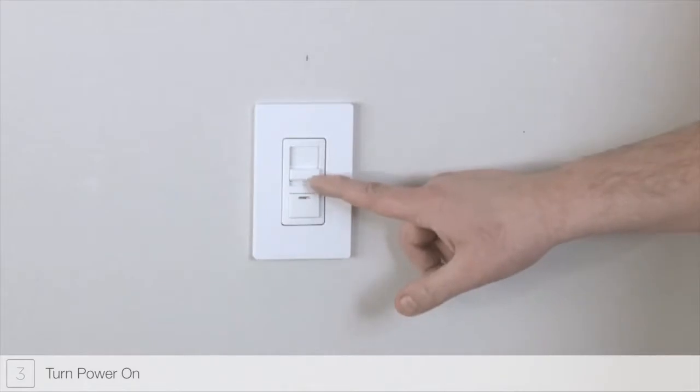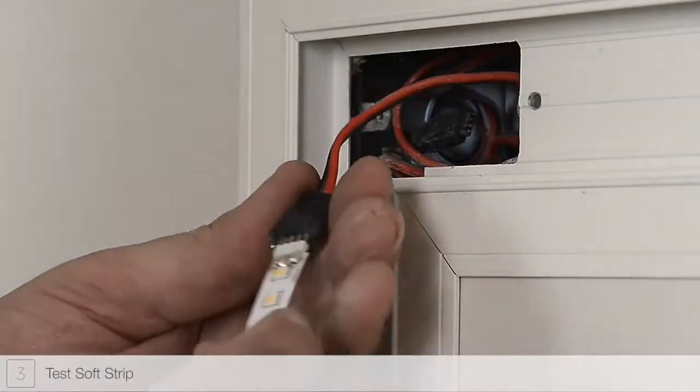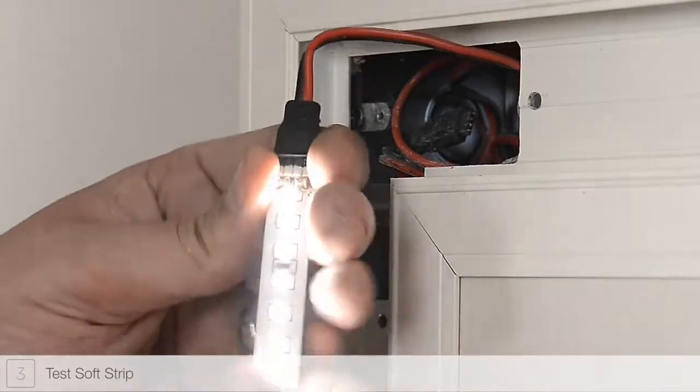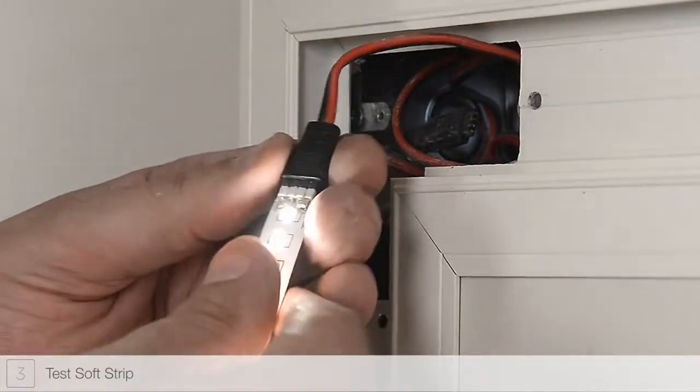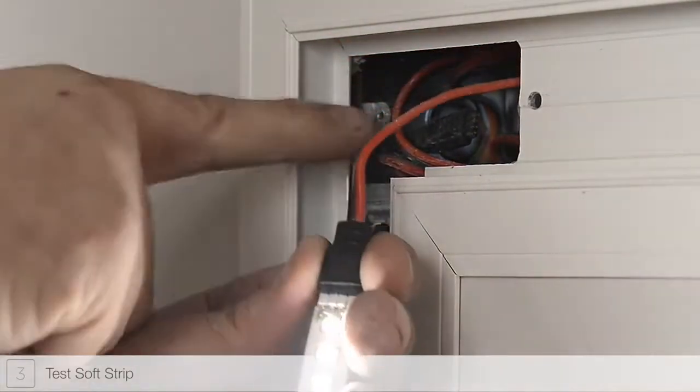Step 3. Restore power to the junction box to test the LED soft strip. When connecting strip to the power feed cable, it is important to align the plus 24 VDC marking on the soft strip with the red wires of the power feed cable.